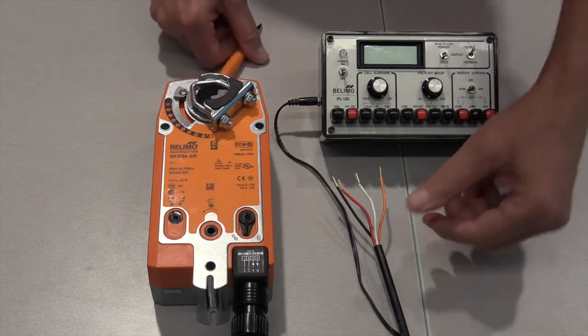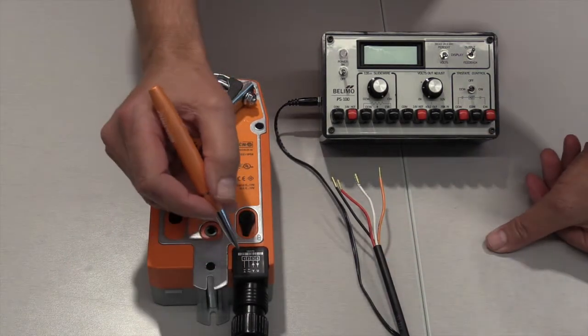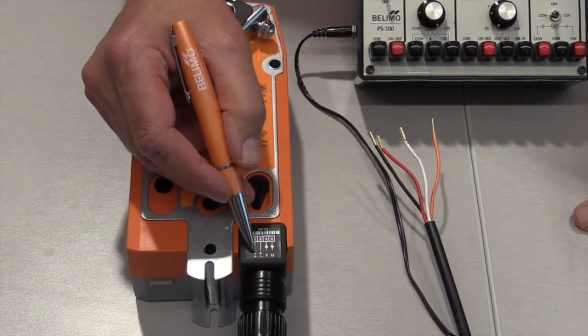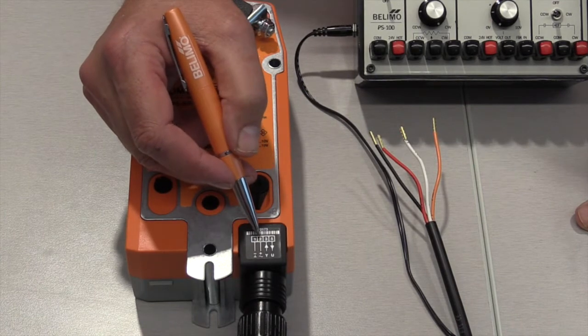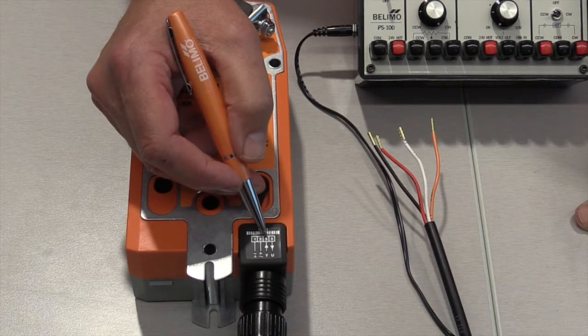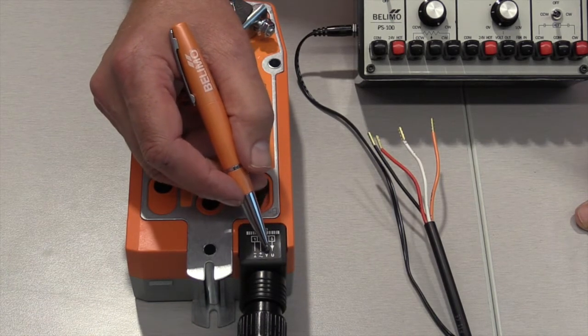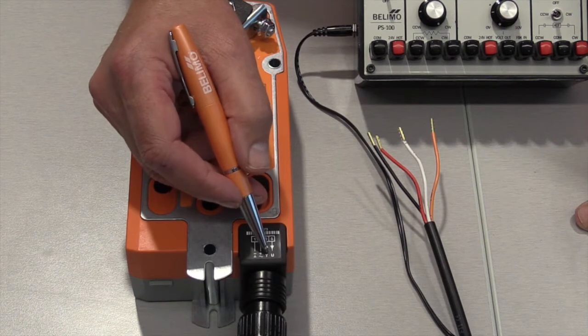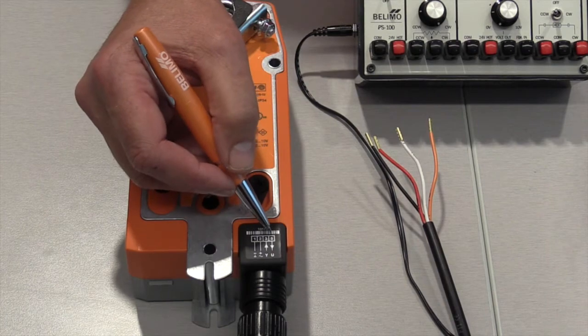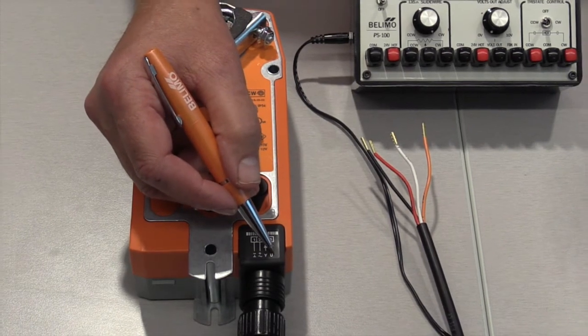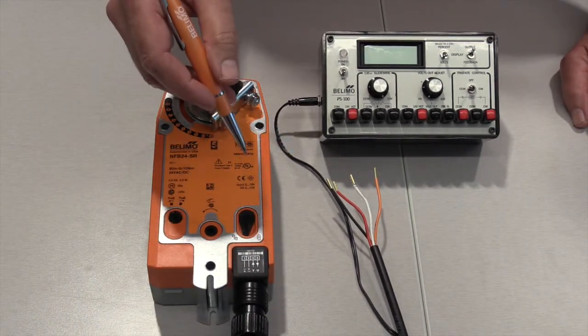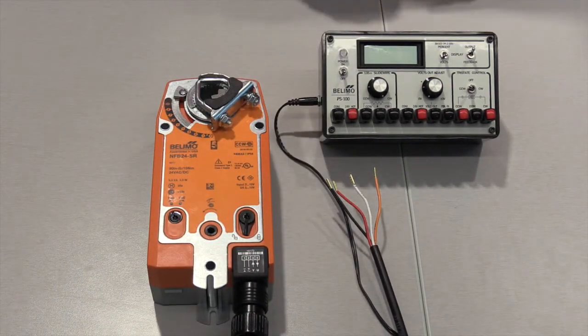It's a 24 volt actuator so I'm able to use the PS100 power supply that puts out a 24 volt power signal. I want you to look on this black portion of the wiring here. We have number one which is the common or negative, number two which is positive or 24 volt hot, number three which is a letter Y and that is the control signal in from the building management system or the PS100 in this case, and the very last one is number five with a letter U and that's the feedback wire that goes out from the actuator back to the building management system or today to the PS100.